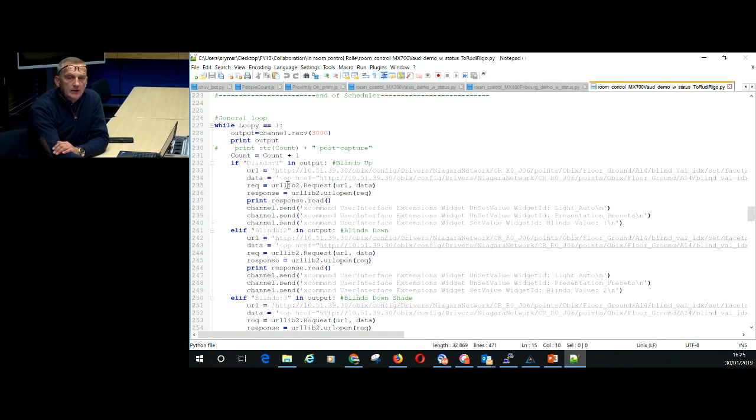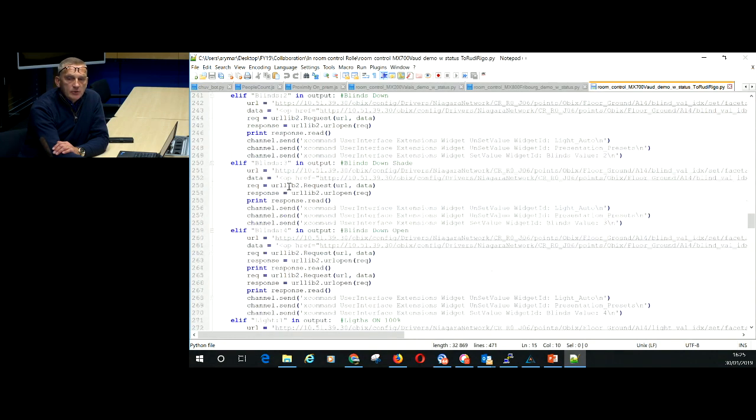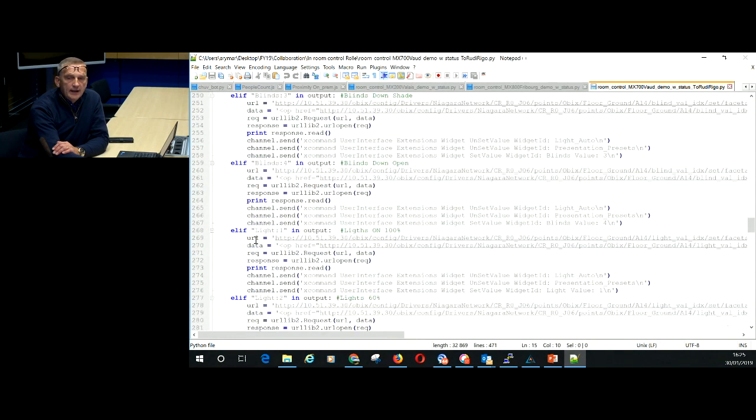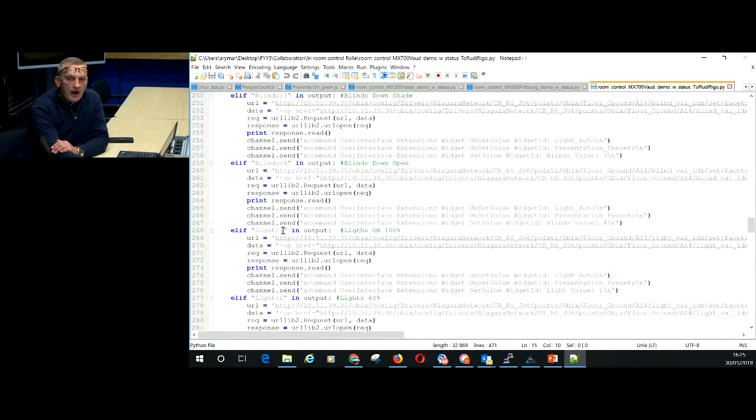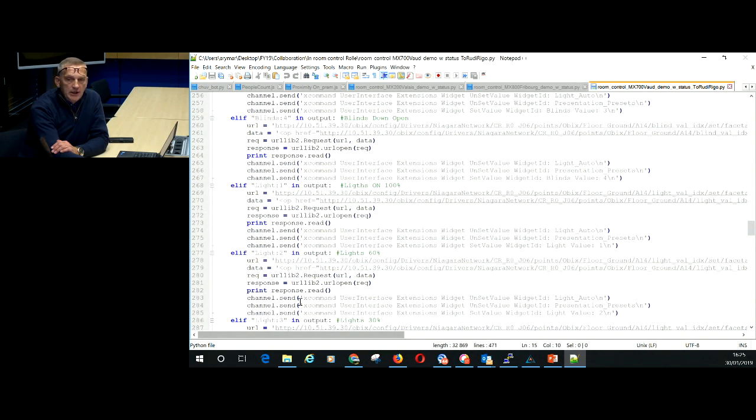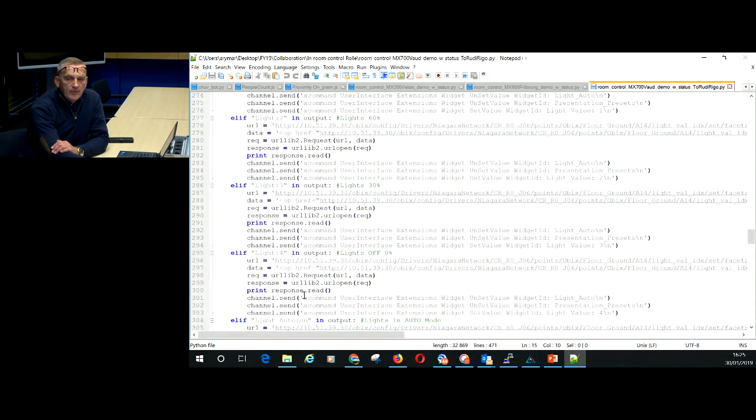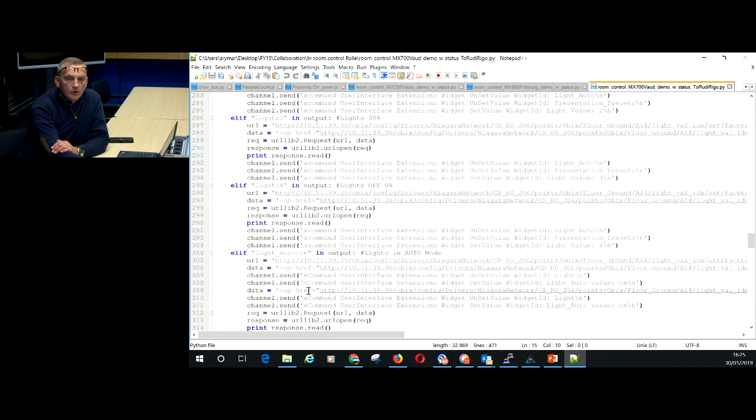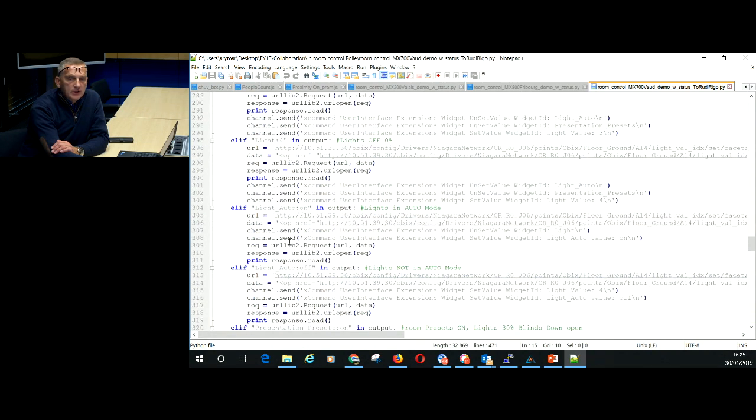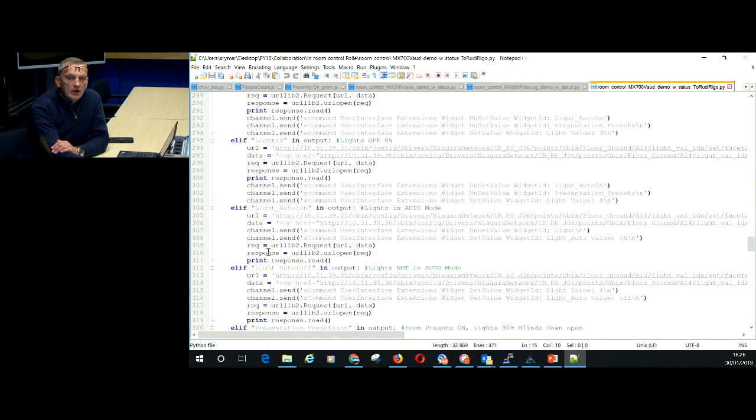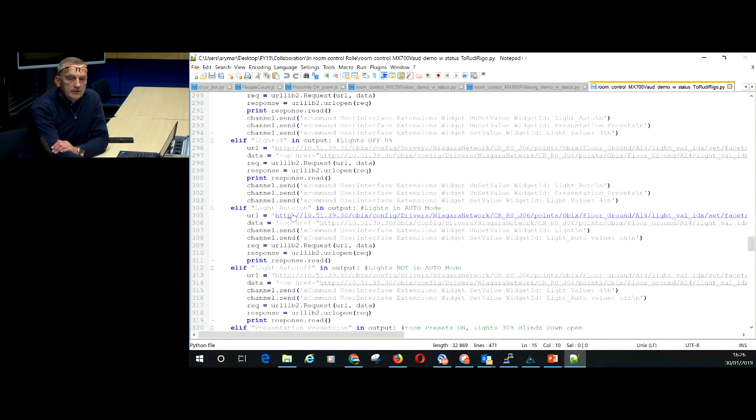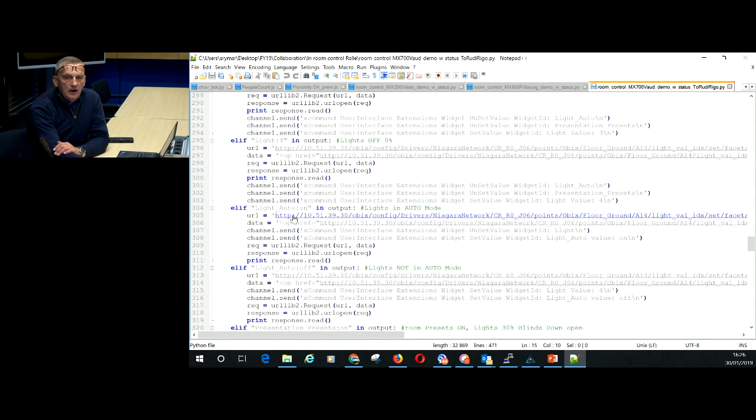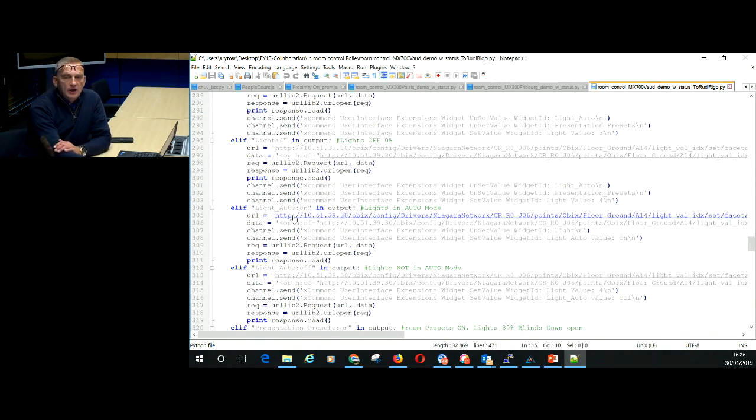I can do it for the blinds. If I scroll down a little bit, I can do it for the lights. So again, a group of four buttons. The widget called light and sub-ID called 1, 2, 3 and so on. And if I want to go a little bit further, if you remember the panel we had before, there is also a light on auto or light off or let's say light auto on light auto off. And if I do that, then I let the BMS adjust the light depending on the outside light of my building. So that's it.